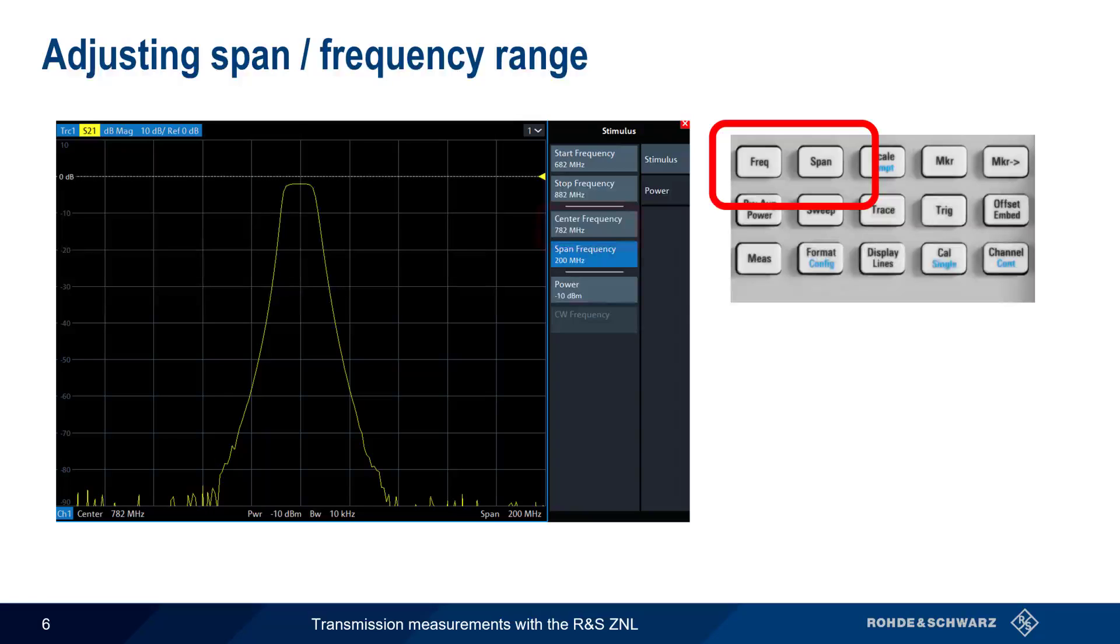For example, we've moved the center frequency to 782 MHz and adjusted the span to 200 MHz, in order to better see the shape of our device under test, here a bandpass filter.